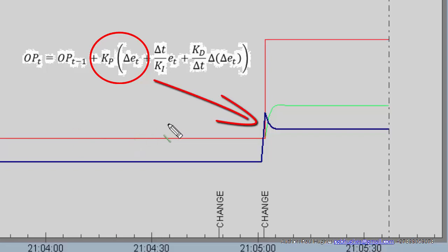So at that time interval there, we had a kick in the set point. That effect that you see there, that initial rise, is the proportional action. Then this decay here is also a proportional action because of change in velocity of the PV. So this is what you would typically see for proportional or PI-D where there's no integral effect.